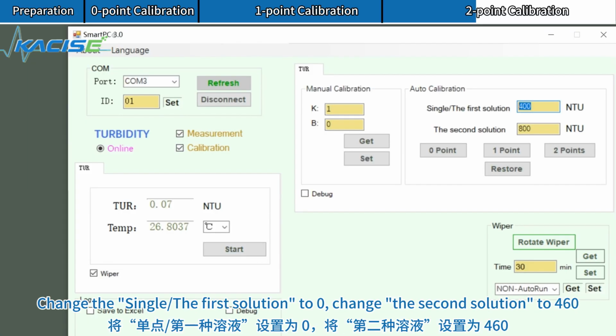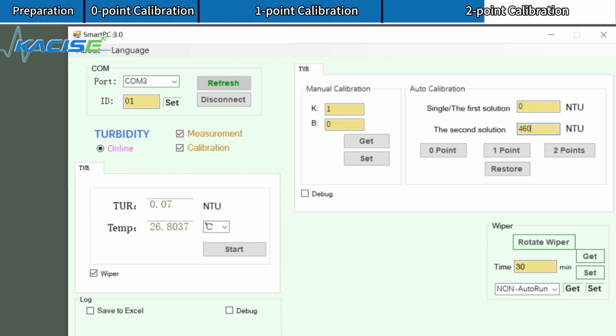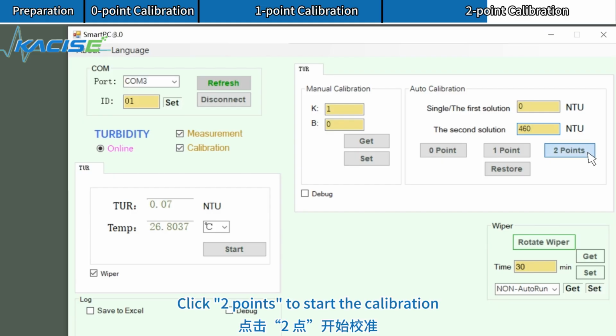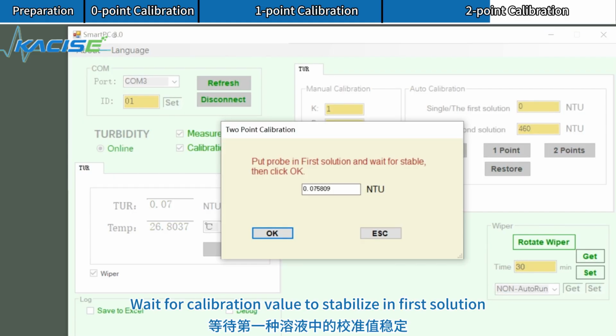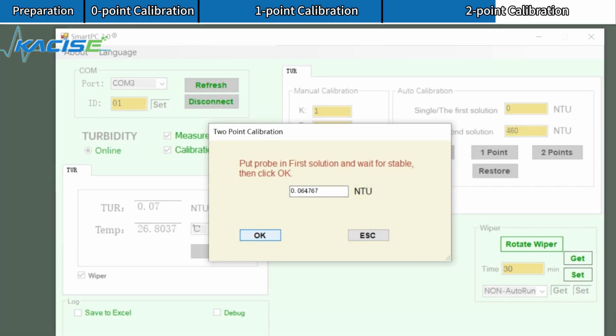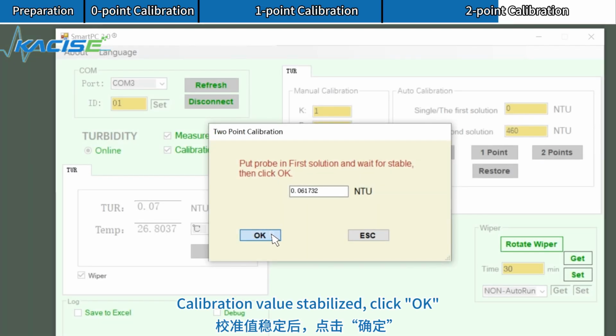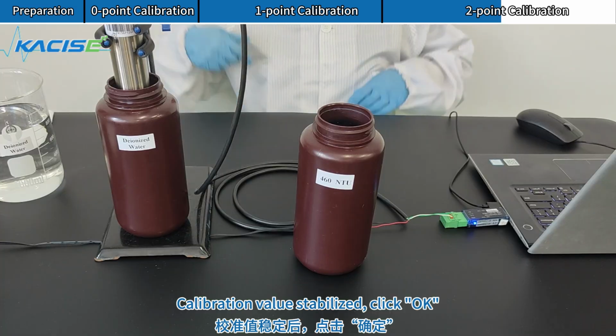Change the first solution to 0. Change the second solution to 460. Click 2 points to start the calibration. Wait for calibration value to stabilize in first solution. Calibration value stabilized. Click OK.